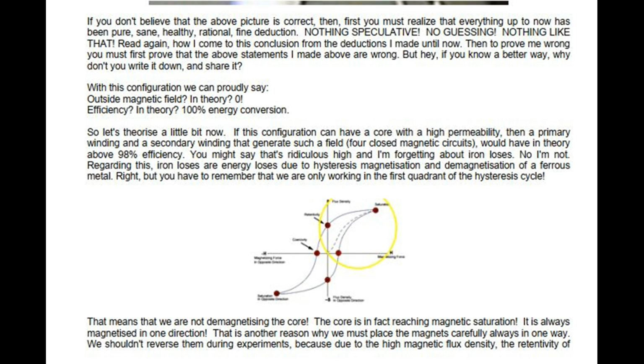You might say that's ridiculously high and I'm forgetting about iron losses. No, I'm not. Iron losses are energy losses due to hysteresis, magnetization and demagnetization of a ferrous metal. But you have to remember that we are only working in the first quadrant of the hysteresis cycle. That means we are not demagnetizing the core. The core is in fact reaching magnetic saturation. It is always magnetized in one direction.